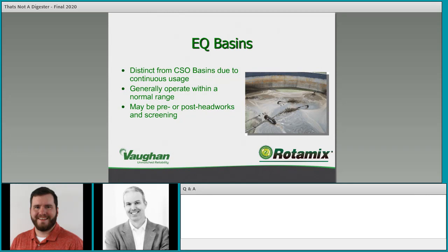EQ basins are generally before primary sedimentation, and all your primary solids will still be in that fluid — those are the most readily settleable within your wastewater. You need good mixing to maintain distribution and make sure you're not overloading your headworks. For example, if your pounds-per-day-under-aeration limit is being exceeded and you're detaining flow to meter it, but then sending very concentrated settled sludge to the facility, you might overwhelm the system anyway.